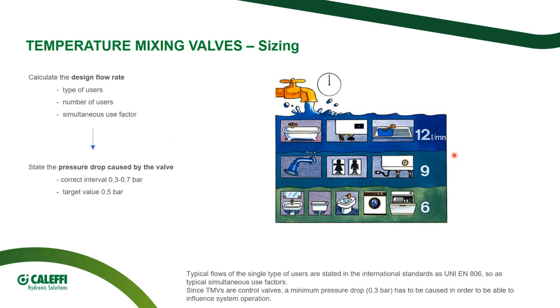The second step is to state the pressure drop caused by the valve. Let's remind ourselves: a thermostatic mixing valve is a control valve, and a control valve has to cause a certain pressure drop in order to influence the behavior of the system. If the pressure drop is too low, it means that my valve is not able to regulate. So the target optimum value of pressure drop caused by a thermostatic or digital mixing valve is half a bar, so 5 meters of water gauge. The acceptable interval starts from 3 meters water gauge and finishes at 7 meters water gauge. So if our pressure drop is within this interval, the valve is correctly sized.